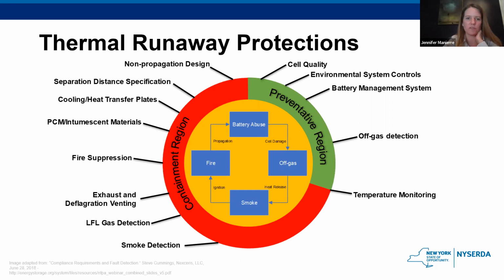And again, if you start at the 12 o'clock mark and work your way around, we're starting with the first things that you want to do to prevent things from happening, like having great cell quality, like high quality batteries, right? And then good environmental system controls. You want to make sure that the room they're in is not going to get too hot or too cold. From there, you want to make sure you have a battery management system. That's the eyes, the ears, the brains of the system that we talked about before. So those are your first basic three things to prevent anything from happening. Even if battery abuse does happen, these are the things that will isolate that cell and cut it off so it doesn't continue to overheat and so on.